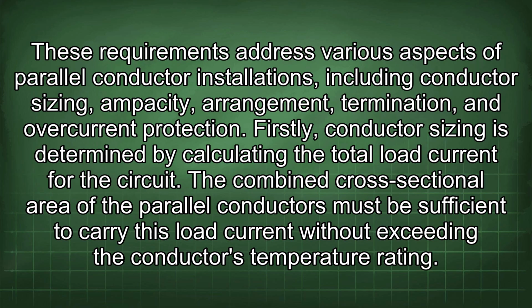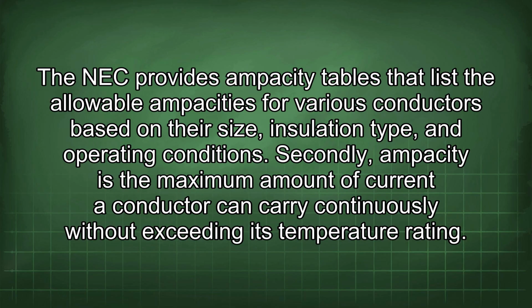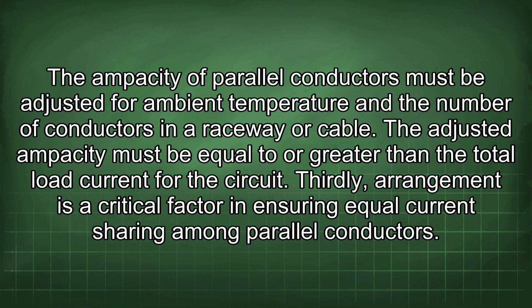temperature rating. The NEC provides ampacity tables that list the allowable ampacities for various conductors based on their size, insulation type, and operating conditions. Secondly, ampacity is the maximum amount of current a conductor can carry continuously without exceeding its temperature rating. The ampacity of parallel conductors must be adjusted for ambient temperature and the number of conductors in a raceway or cable. The adjusted ampacity must be equal to or greater than the total load current for the circuit.